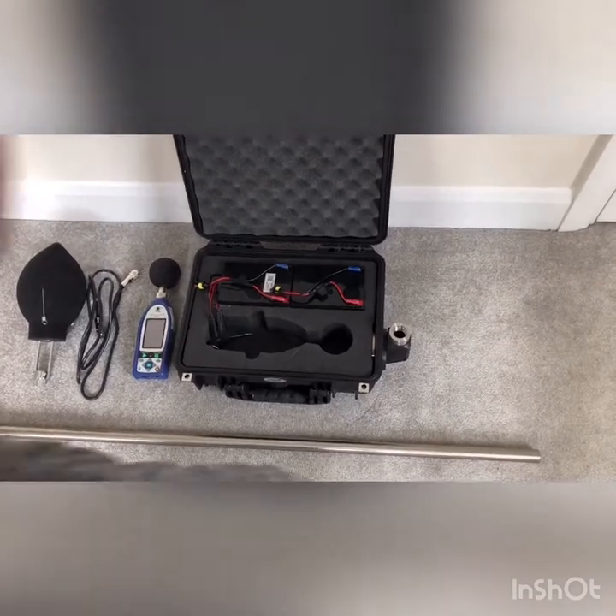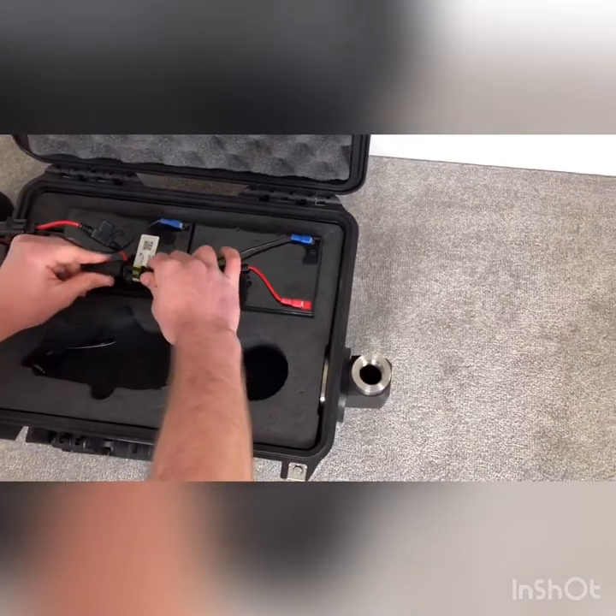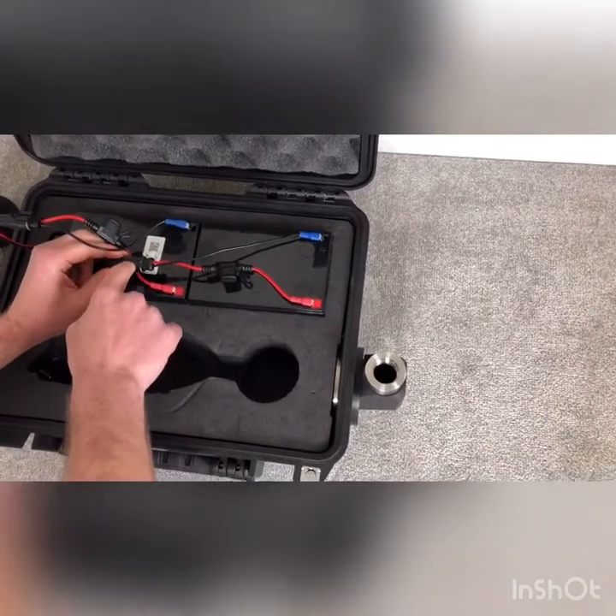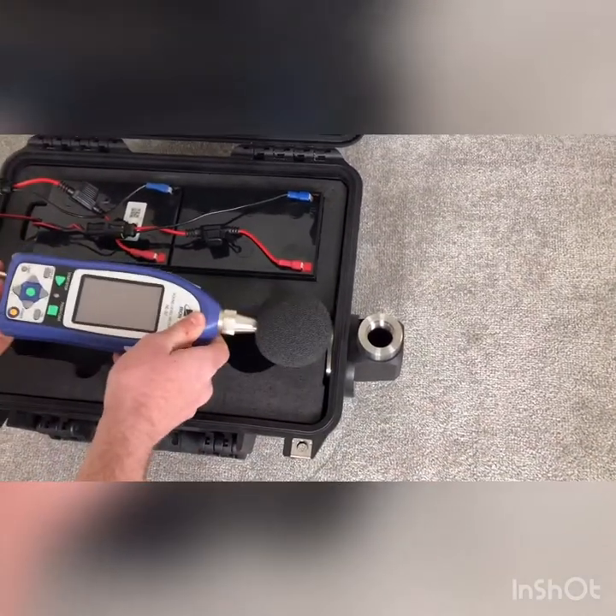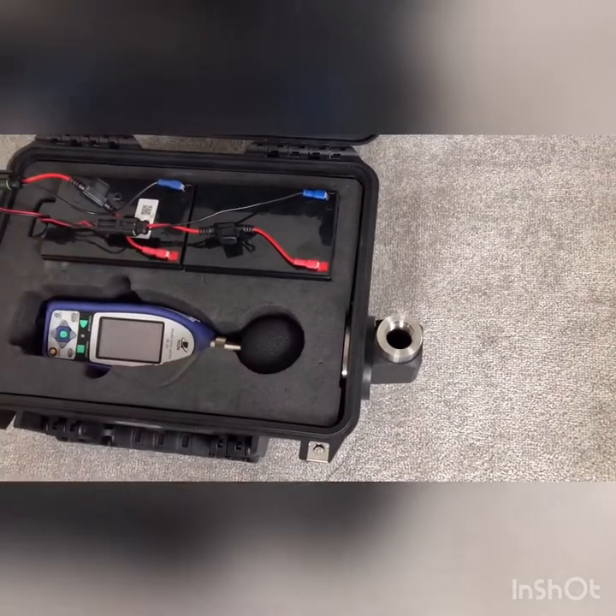The first thing to do is make sure your batteries are connected up — just clip them in. You can't get the batteries wrong because there's a specific clip they have to go into. Then place your NL52 into the Peli case, plugging it into the power, and leave it there for a moment.